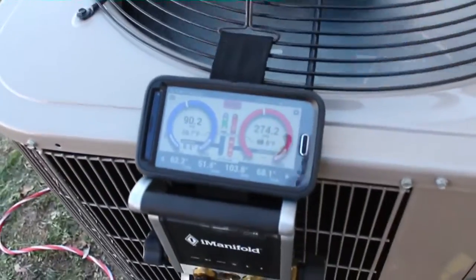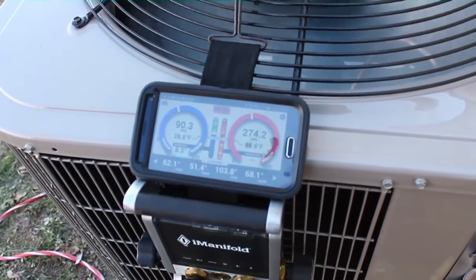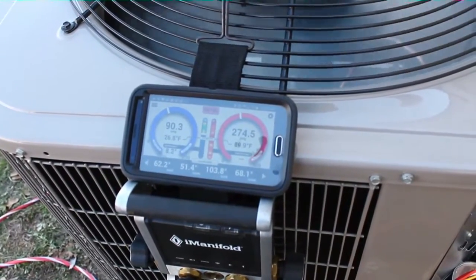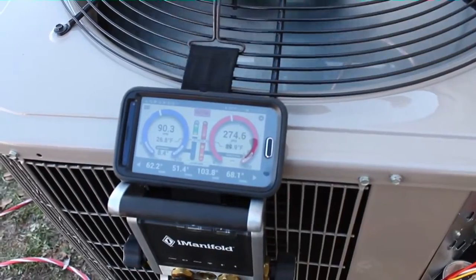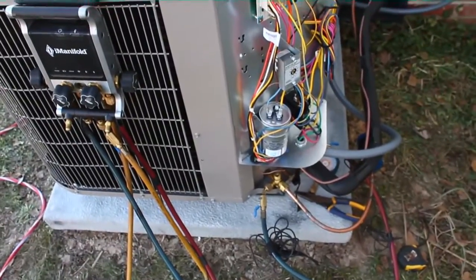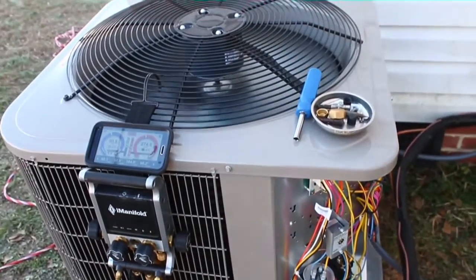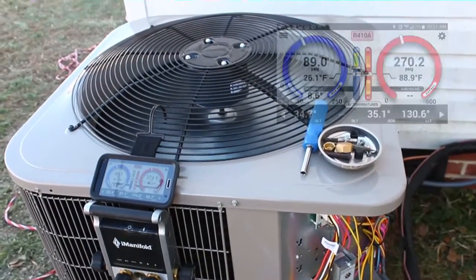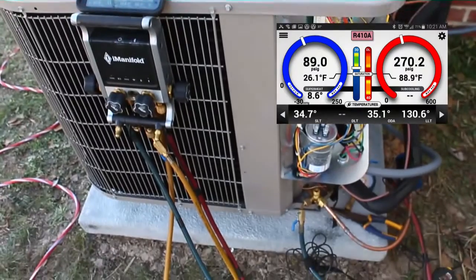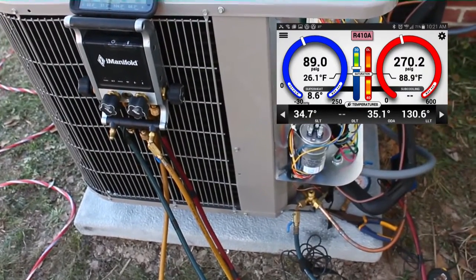Our suction pressure is a little bit higher than the chart. But again, the temperature's probably gone up a degree or 2. And we are 274 at head pressure. Right in the ballpark. Close enough where I probably won't do anything on it. I'd take a look at it in the spring and just fine tune the charge, because heating charge is not as exact as cooling charge.